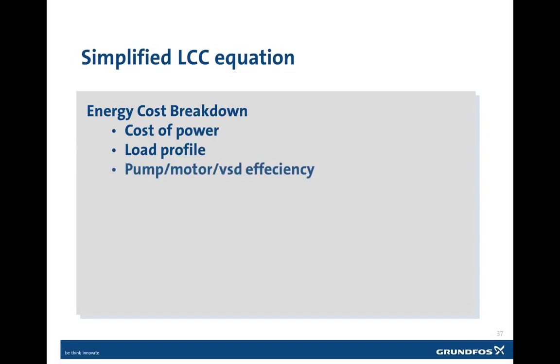Then we also have to think about the efficiency of the pump and the motor, as well as if a variable speed drive is used in the application. Then we also have to consider the control method that's used for operating and running the pump. And then we also have to consider the number of pumps that are utilized in the system. So a summation of all these different factors will provide us with a true life cycle cost picture for the application.